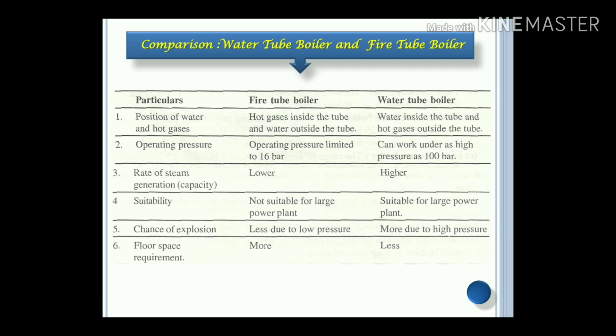Comparison of water tube boiler and fire tube boiler. According to the position of water and hot gases: in a fire tube boiler, hot gases are inside the tubes; in a water tube boiler, water is inside the tubes. Operating pressure: in a fire tube boiler, it is limited up to 16 bar; in a water tube boiler, it can be high pressure up to 100 bar. Rate of steam generation or capacity: fire tube boiler has a lower capacity compared to a water tube boiler. Suitability: fire tube boiler is not suitable for large power plants. Regarding explosion risk: fire tube boiler is less explosive because of its low pressure; water tube boiler is more explosive due to the high pressure.